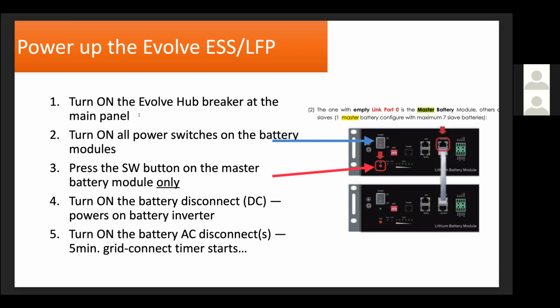Because the battery system itself can be completely powered down with the disconnects turned off, if that grid voltage is applied with the 40 amp breaker, it will pass through the hub ATS circuit and power that backup loads panel and the PV that's on it, as well as the loads.